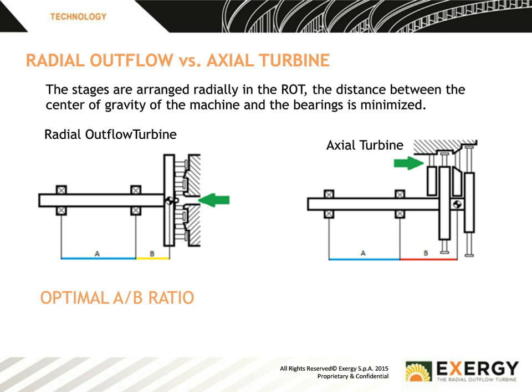Small blades create a lot of turbulence at the tip and at the inside. Large blades, you end up with very high speeds at the tip and also weakness within the blade. So the only expansion ratio advantage you have with the axial turbine is with blade height. Whereas with the radial outflow turbine, as previously explained, you have both blade height and expansion across the disc. So you have this very good expansion ratio. So really the reasons we have this excellent efficiency are larger number of stages, better expansion ratio, and, as I've already mentioned, the lower vibrations.